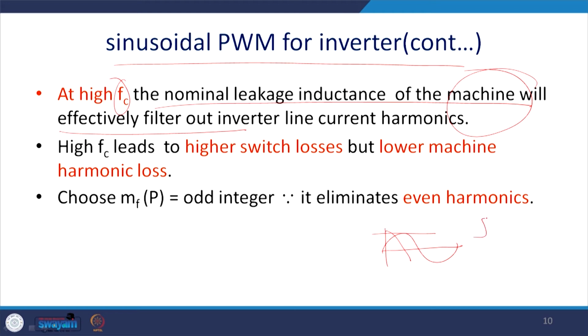Since you've got PWM pulses, your dV/dt is very high, and due to that leakage current will flow. There's a capacitance between different points of the machine because of the different voltages at different parts of the machine, and you have to ground it for operator safety. Ultimately, C dV/dt is the current, so high leakage current will flow, and that will essentially damage the insulation of the machine.